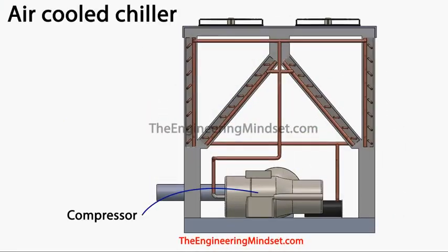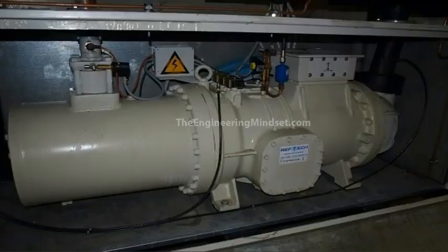And the next part we'll look at there is the compressor. So the compressor is obviously the driving force of the refrigerant around the system. In this case, I've just put a screw compressor in here. It's usually a screw or a scroll or reciprocating. So a real screw compressor will look something like this.